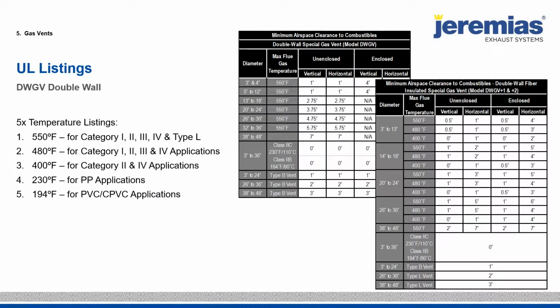Some options on the gas vents. You actually have 7 different temperature listings, and we actually, like everyone else, they choose either 550 or 480, but we actually went down to 400 because condensing boilers today, they never exceed 360 degrees Fahrenheit.